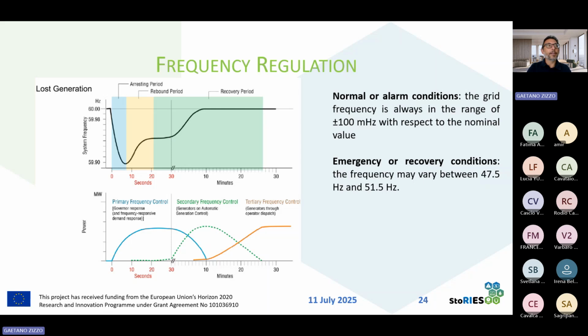So we are still working, but no more with the rated frequency. Then we have the secondary frequency regulation, that is the one that adjusts the value of the frequency and brings it to the rated value. And then the tertiary frequency regulation, where the generators are dispatched by the centralized control in order to restore the balancing resource of the system. Well, storage systems can be used in all three stages of frequency regulation. Anyway, we will focus in this case only on the first part of the frequency regulation, only on primary frequency regulation.